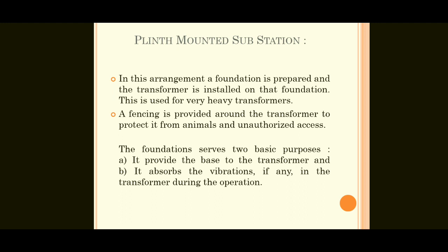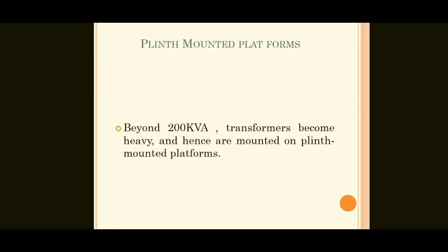So around this plinth mounted substation transformer, some fencing is provided to protect from animals and unauthorized access. Next, plinth mounted platforms. Beyond 200 kVA, transformers become heavy and hence these are placed on plinth mounted platforms.